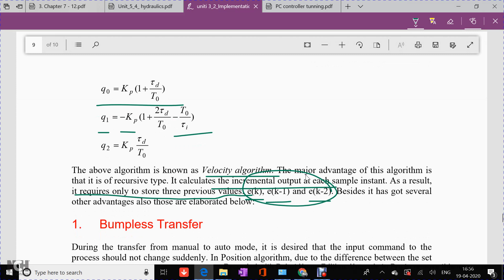Besides requiring only three stored values, the velocity algorithm has several other advantages. The first is bumpless transfer — a basic requirement of any PID controller. When a controller is transferred from manual control mode to automatic control mode, it can experience a jerk called a bump. This unexpected change in output should be avoided, and the velocity algorithm is very efficient in achieving bumpless transfer.